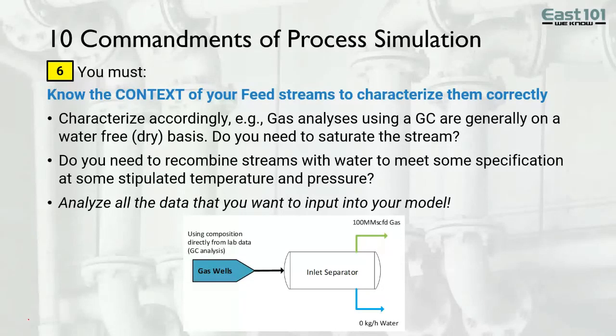If you're taking a look at some results and they're coming out of a GC, you will find that they're always going to be on a bone dry basis. There's no water. Why? Because before you put your sample into the GC, you need to get all the water out. Otherwise, you're going to damage the inside of the GC. There's some tubing with some beads. If you have water in your system, you're going to essentially damage your equipment. So most of the time for a GC, you'd knock all the water out, so you'd have a bone dry gas coming out. Hence, your GC analysis would be water free.